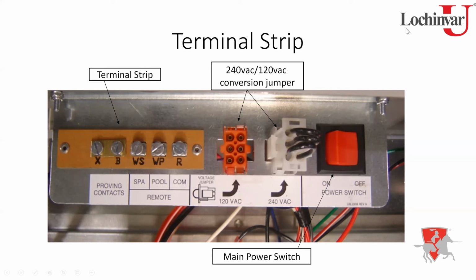What I've had happen before is on startup they had a low air pressure switch issue, you know, APS open, low air, it's not working, lockout. But they wired it for 120. They forgot to take that jumper plug over to the 120 position. So what'll happen in that situation is that fan will get power, but it will run very, very slow, and it won't have enough energy to pop that pressure switch closed. So just something else to keep in your back pocket: brand new startup, low air situation, and you barely hear that fan run, check that jumper plug just to make sure.